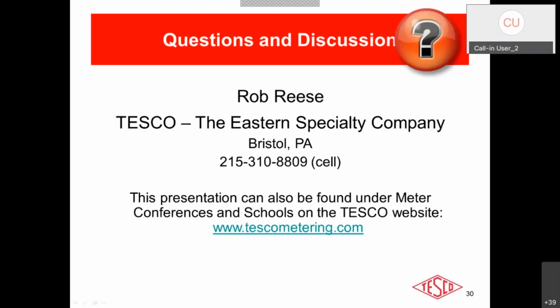If you don't have a matched set of CTs in regards to manufacturer and model, then your ratios could still be good. And so I wouldn't be worried about it, but because they are a different model number, different manufacturer, different manufacturing techniques and materials, you could have differences between the phases for admittance, but it's not really affecting the performance of that installation, and you still have correct billing.